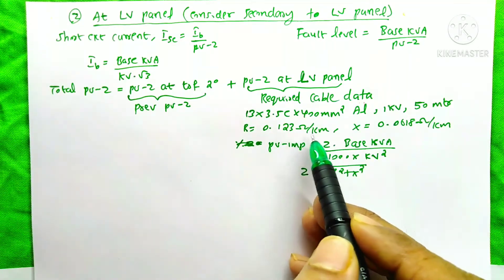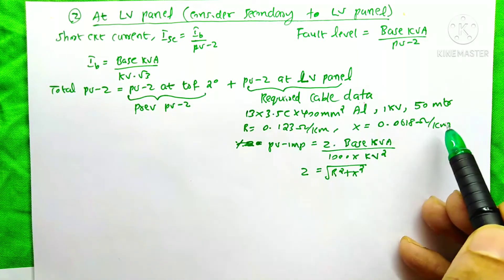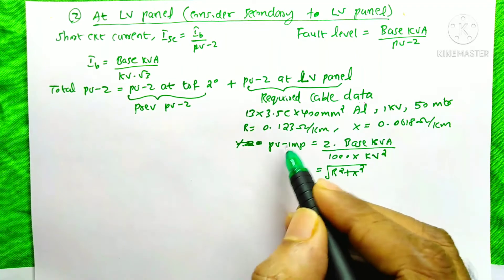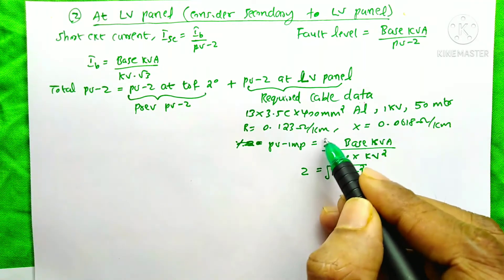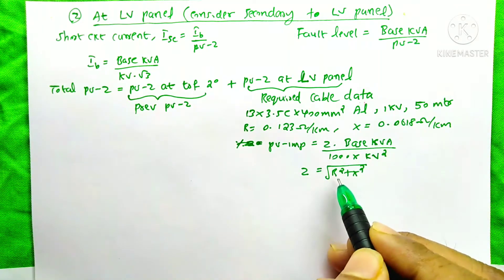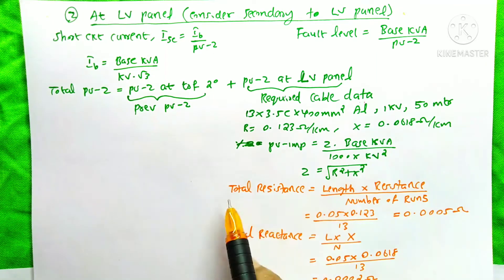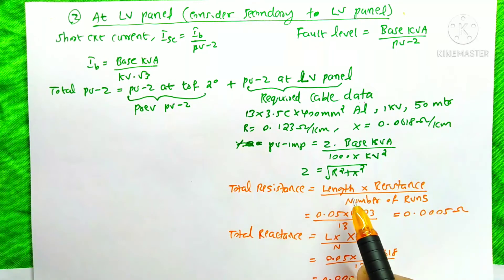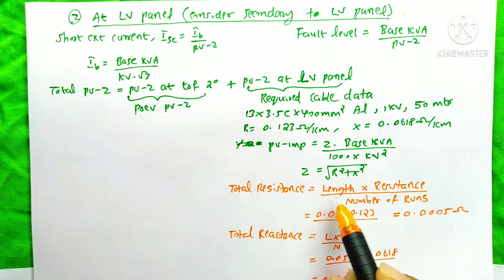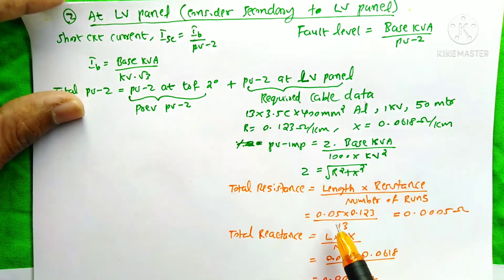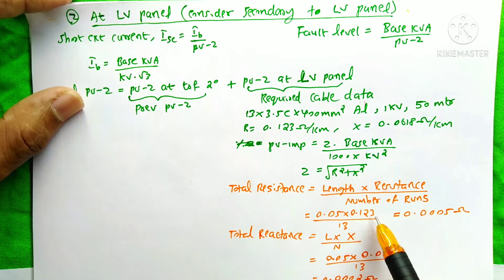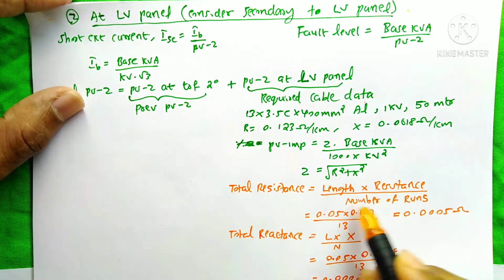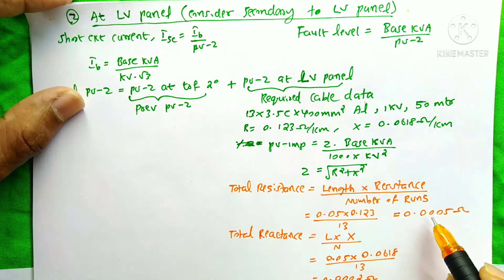The per unit impedance at the LV panel equation is Z into base kVA divided by 1000 into kV squared. First we find Z, the cable impedance, using root of R squared plus X squared. The total resistance equals length of cable multiplied by resistance of cable divided by number of runs: 0.05 km into 0.123 Ohm/km divided by 13, which gives 0.0005 Ohms.